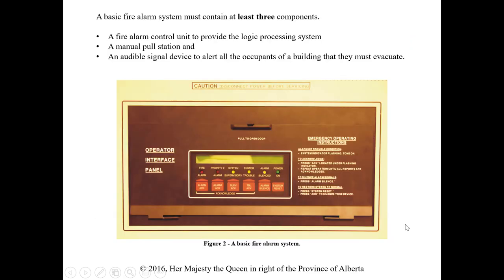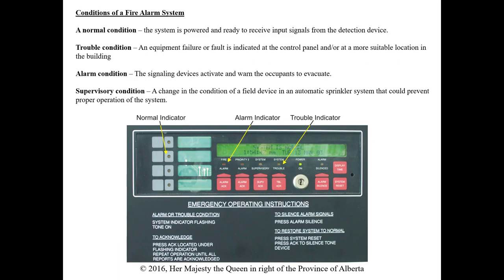In a basic fire alarm system we need at least three components. First, the fire alarm control unit provides logic for the processing system — it makes decisions when it sees a change in state from a field device. Second, a manual pull station gives us at least one way to manually initiate an alarm. Third, an audible signal device alerts all occupants that they must evacuate, whether triggered by a pull station or another field device.